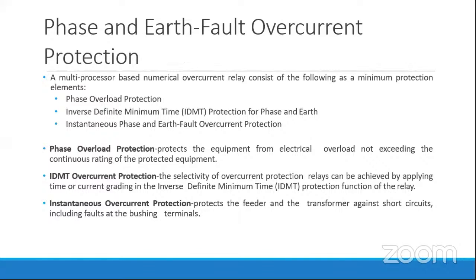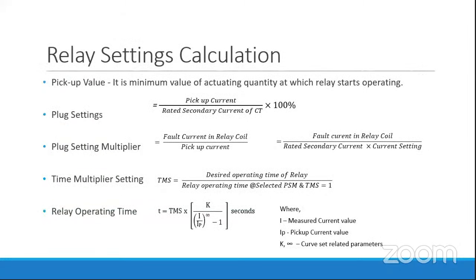In order to protect these equipments, we need to give certain settings to the relay, such that if the parameters go beyond this value, then the relay should operate and raise a command to detect the fault and isolate the faulty section. So this is the relay setting calculation, and that is how the relay setting calculations can be done.